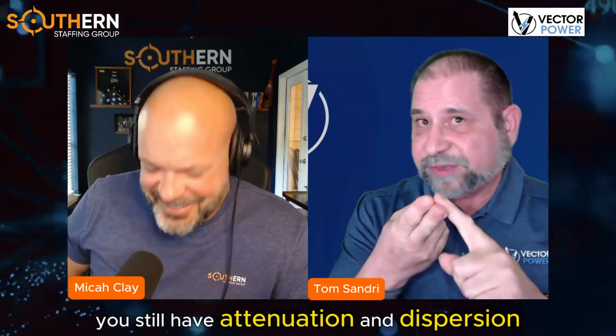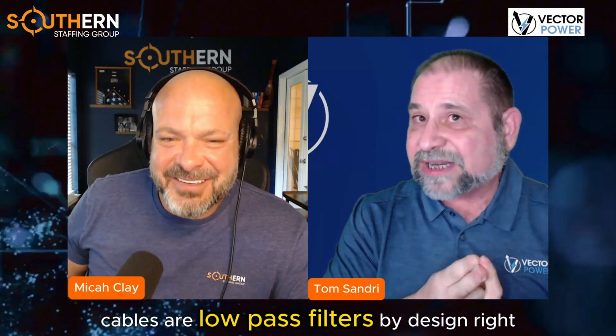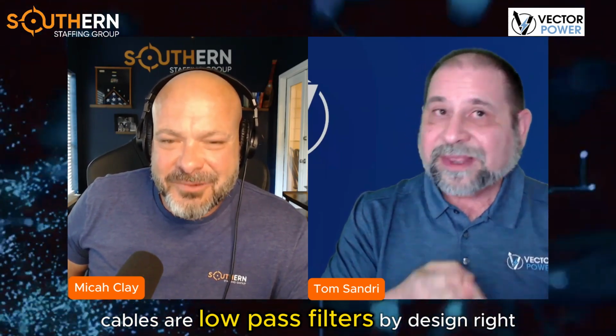That's gone. Well, let me ask you this: how are you doing the mapping on that 5 picocoulomb signal? You still have attenuation and dispersion. Cables are low pass filters by design, and you can't control the lengths. You've got to get through all the splices and everything else. And like you said, if you don't have a return signal, you have nothing to work with. So how are you going to map it?